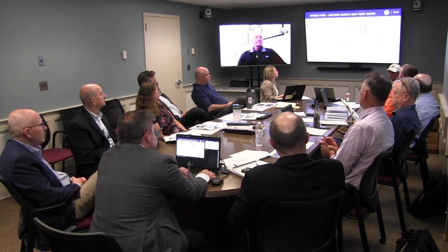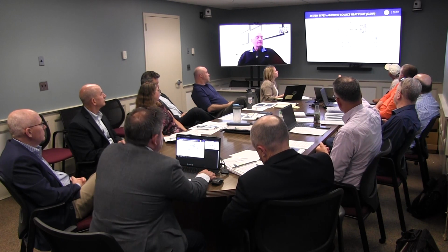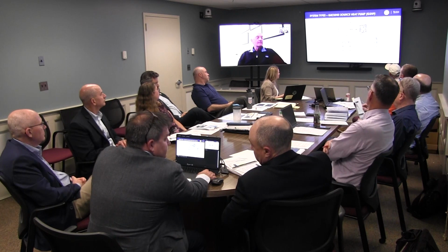Typically, putting these things above the ceiling is an option, but they can't go above the ceiling of the classroom because of noise. Ceilings above the corridor would have deeper cavities, and then maintenance becomes a nightmare when you have to go above the ceiling. So it's not practical to do that, although it can be done. In that particular picture, there is one unit above the ceiling in the corner by the exterior window. That's the only one in that entire project, but it was because we ran out of floor space. You can also create a bigger mechanical space and put a bunch of them in there, but then you're running a lot of ductwork around. It's just a matter of what you do with real estate within the building.